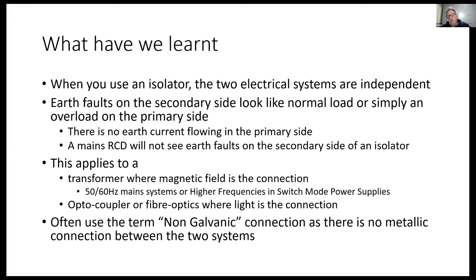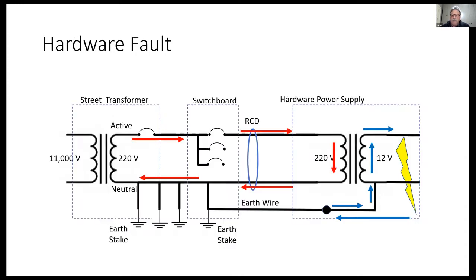We use the term galvanic connection. So this is non-galvanic, because there's no metallic connection between the two systems. In this case, it's actually the primary winding: the electrons in the primary are creating a magnetic field, and the magnetic field is coupled to the secondary coil and creates current there. There's no metallic connection between the two.